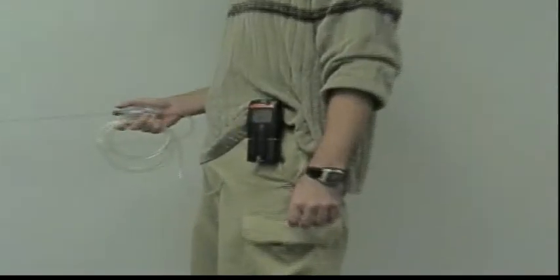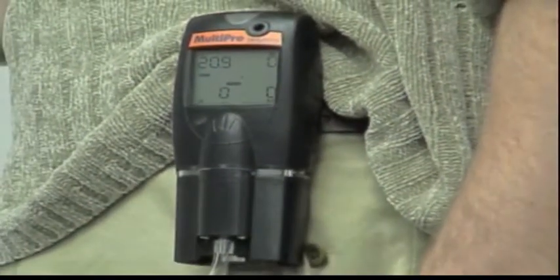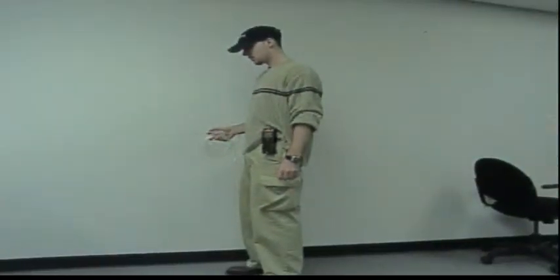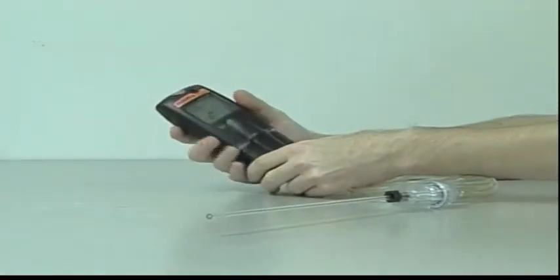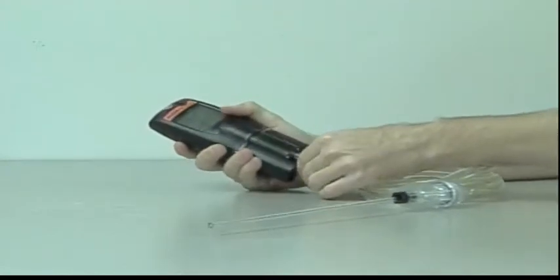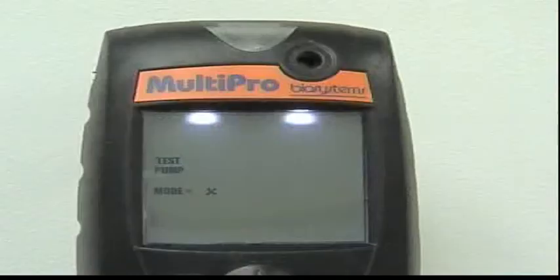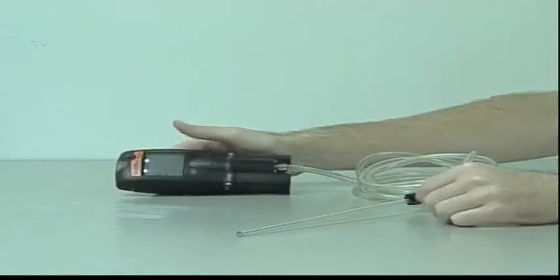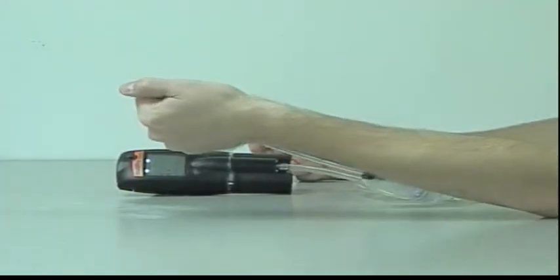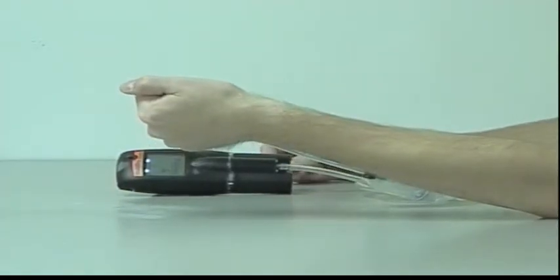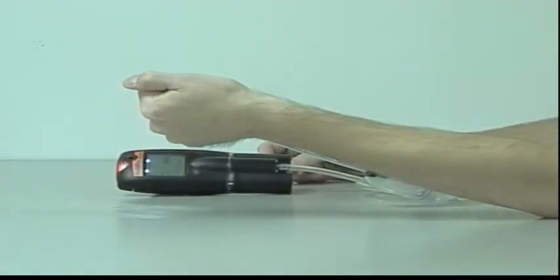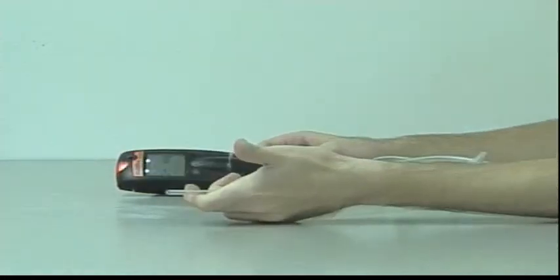For long-term remote sampling applications, an optional built-in motorized continuous sample draw pump is available. To turn the pump on, simply attach it to the instrument and secure it with the knurled screw. The MultiPro will automatically recognize the pump and will start the pump initiation sequence. Block the pump inlet by placing a finger over the end of the sample probe assembly. Once the MultiPro recognizes that the sample has been blocked, it will instruct you to remove the blockage.